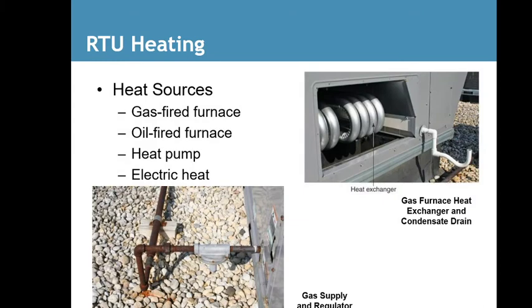Rooftop unit heating is just like a standard unit that either is on the ground or a package system or a split system. There's going to be gas-fired furnaces, which is more common on the coastal states because we find a lot of natural gas in that area. Oil-fired furnaces, heat pumps, and electric heat. Very few businesses, depends on what kind of business, but very few businesses need a lot of heat in the winter, even when it's cold.